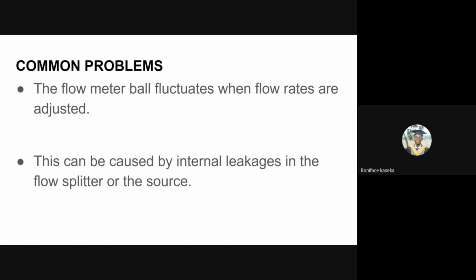Sometimes the flow meter ball may fluctuate when the flow rates are adjusted. For example, you may be in a scenario where you want to deliver, let's say, 1.5 liters per minute of oxygen to a patient. Instead of the ball resting at 1.5, it is fluctuating between, let's say, 1.3 and 1.7. That is a problem, because it means you're not delivering the precise amount of oxygen that the patient needs, and that can be fatal.